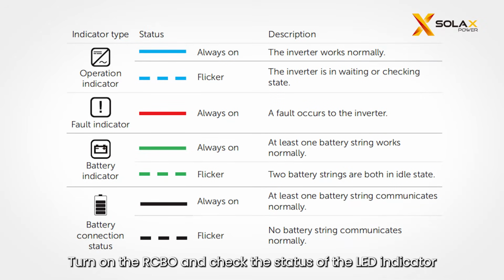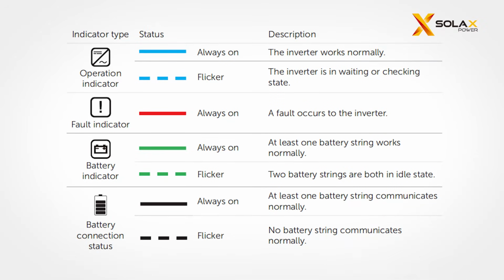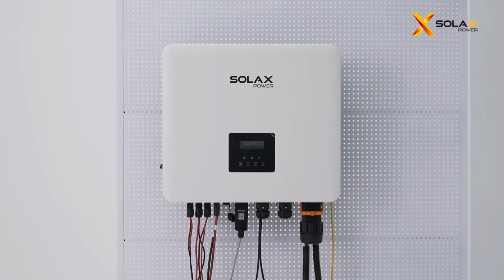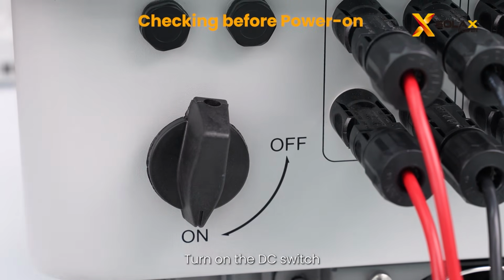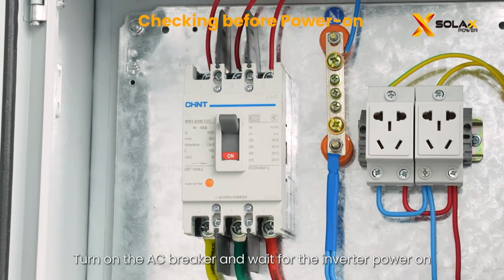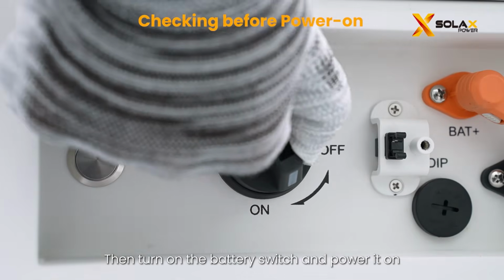Turn on the RCBO and check the status of the LED indicator. Turn on the DC switch. Turn on the AC breaker and wait for the inverter power on. Then turn on the battery switch and power it on.